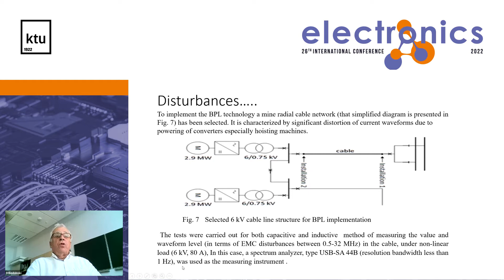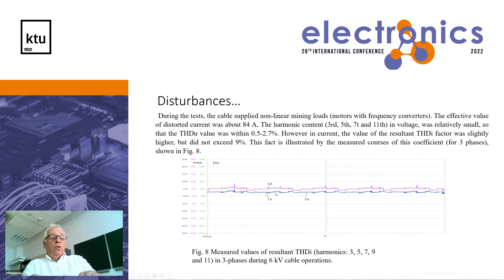And we found out that, about the load, the THD, total harmonic distortion, of the voltage was relatively low and was within the accepted limit, up to about 3% is accepted for the voltage. The voltage waveform is not usually distorted. However, current sometimes can be tremendously distorted, but also in these cases was not too high. It didn't exceed about 9%. Therefore, you can see that the measured value of resultant THD for the different harmonics will appear between 3 to 11 in 3 different phases, L1, L2, and L3 respectively, under the cable operation.